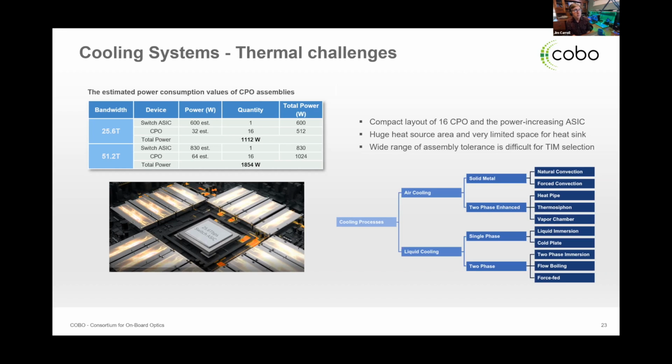And these figures, they're generated theoretically, right? It's not lab testing yet for these. So they were generated theoretically. The company that did all the work, Ragile, also demoed that design at OFC, and I believe they're doing it elsewhere. So if someone is interested in that, you can just let us know, and we can get you in contact with the right people to get more details on that. Okay, and can you remind us for that Ragile one, the cooling system that they used, was it air? No, they used a cold plate, so a liquid cooling system, to fit it all within a 1RU switch design.